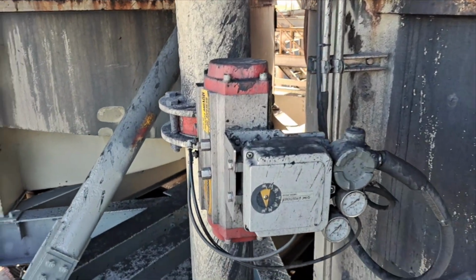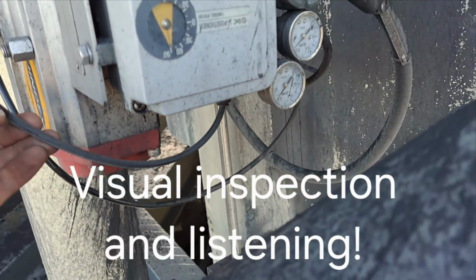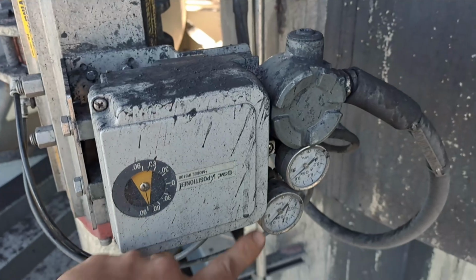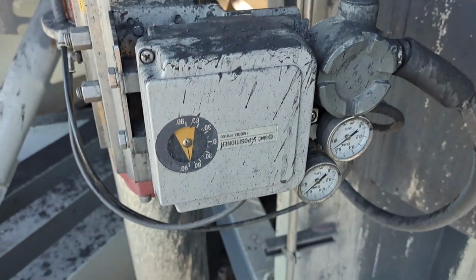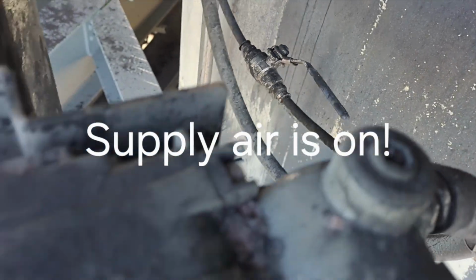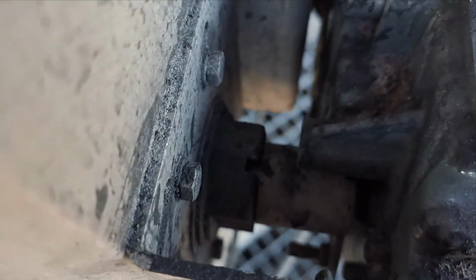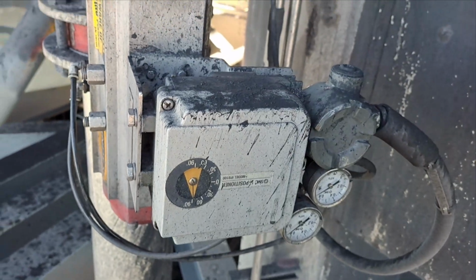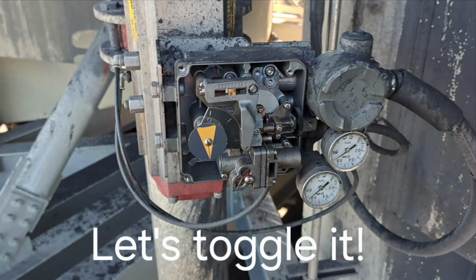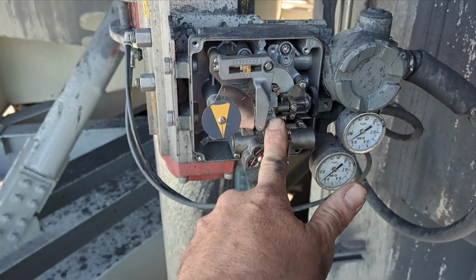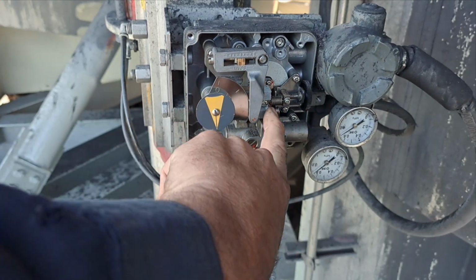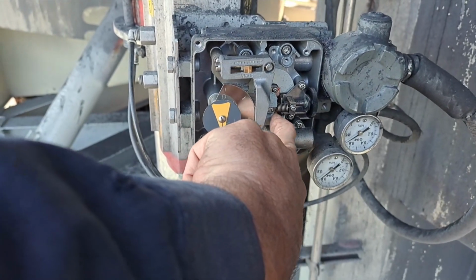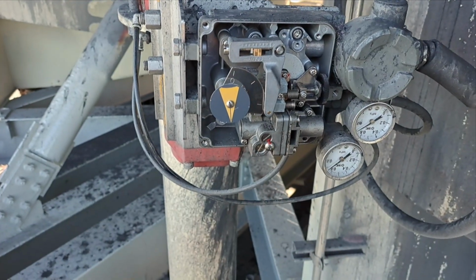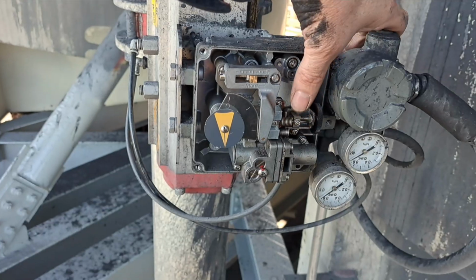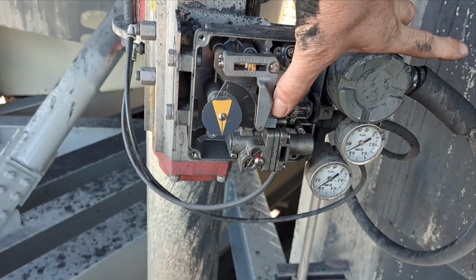As I approach the control valve, my initial assessment involves looking, listening, and inspecting the setup to ensure everything is as it should be. My initial inspection didn't reveal much, so the next step is to pinpoint where the fault lies: pneumatic, electrical, or mechanical. I start by toggling the counterweight on the leaf spring. If the valve moves, the issue is upstream from the pilot valve. In this case though, it doesn't, which leads me to suspect that the pilot valve is the culprit.